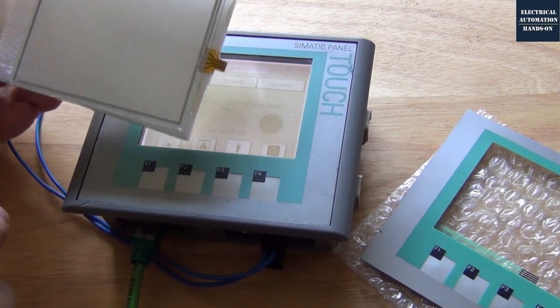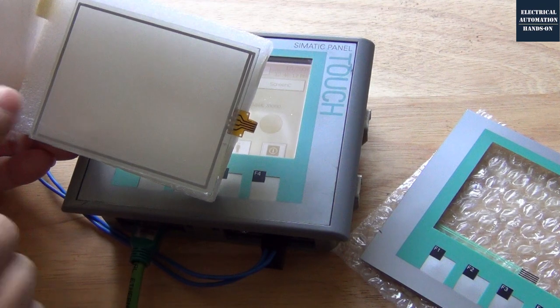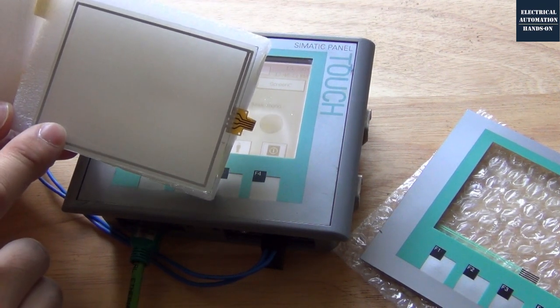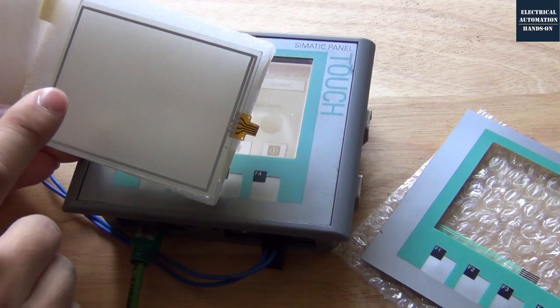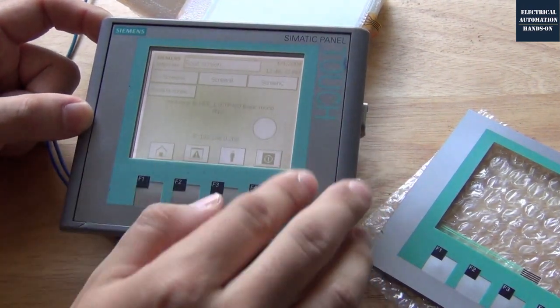Basically like this screen, the problem comes from this screen that failed. So I need to replace this screen. We need to tear down this HMI and replace this screen. Or if your HMI also has a button problem, we can replace this film and also replace this glass screen.